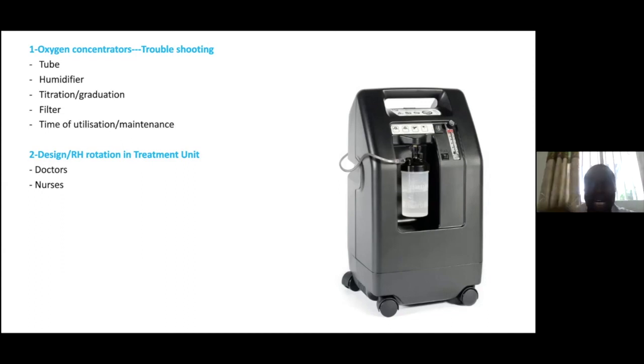So I moved around and checked all the oxygen concentrators, and I found the majority of our problems were related to troubleshooting. It is just checking, when the patient is on the oxygen concentrator, whether the tubes are blocked anywhere, or whether the patient is properly lying down but compressing the tube, or whether there is leakage anywhere, or also the maintenance. The oxygen concentrator also needs a maintenance plan, because we have the filter on the back of the concentrator that needs to be checked at a set frequency, so there should be a proper maintenance program. If the oxygen concentrator is running 24 hours a day but there is no maintenance, no checking of the circuit, no checking of the tubes that bring the oxygen to the patient, it is a big problem. And this is the majority of the cases that I have found.